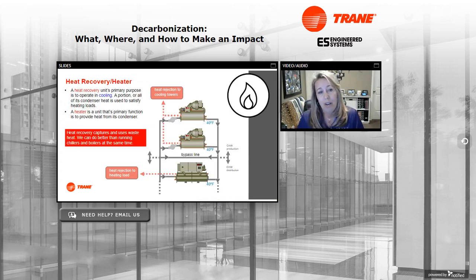So first, let's talk about heat recovery and heaters. Heat recovery is one of the simplest solutions for electrification. We're really taking heat that would normally be treated as waste and rejected to a cooling tower, and we're reusing it to satisfy a heating load within our building. While we typically think about heat recovery in water-cooled applications, we can also do partial and full heat recovery in air-cooled chillers as well. This is typically done with a desuperheater or a secondary heat exchanger.